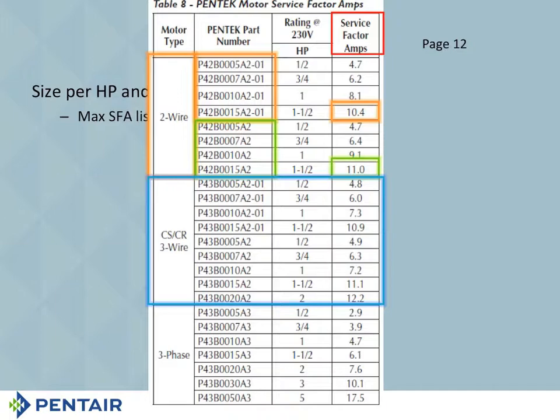Okay, and that's what that blue line there represents, it's got the CSCR. Remember, you do have CSIR, and of course, you don't want to use that max load amps there. The reason you don't want to use those max load amps is because they're going to be higher than CSCR, because you turn off your start windings. With your CSCR, you're using your start winding all the time, and that's why you're running lower amperage through there. So make sure you're doing that.